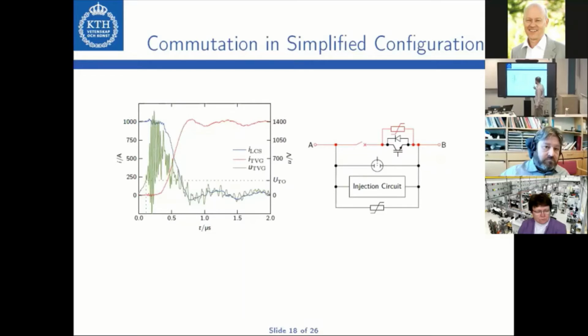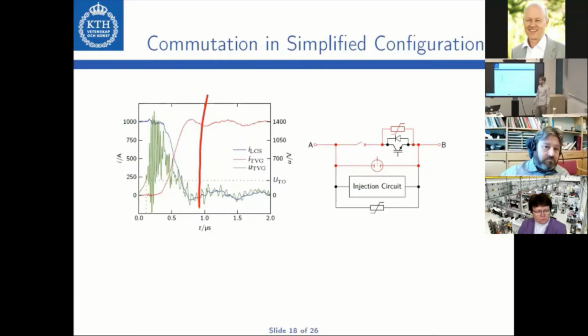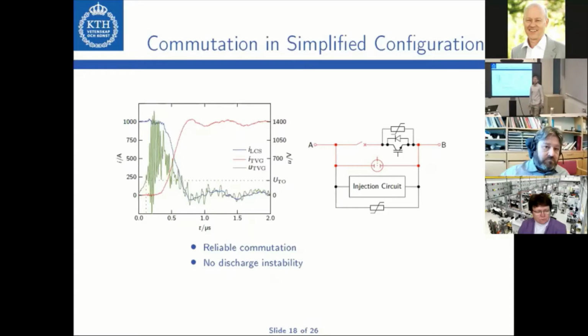When the snubber voltage, and hence the triggered vacuum gap voltage, increases beyond some level, which exceeds the minimum voltage requirement, the triggered vacuum gap can be triggered. You can now see substantial oscillations in the arc voltage. Nonetheless, within not even 1 microsecond, the current commutates from the main path to the commutation path and hence the triggered vacuum gap. And we found that this is a very reliable commutation process. In fact, it never exhibited these kinds of instabilities we observed for the originally proposed configuration. We have also tested this at various current levels, and it was equally reliable at all current levels.